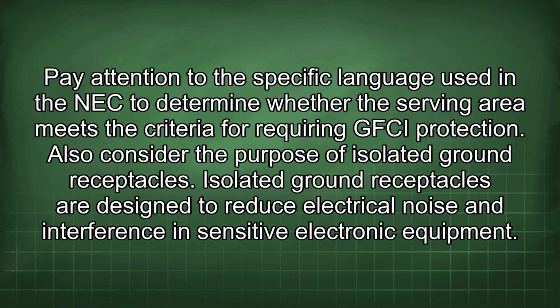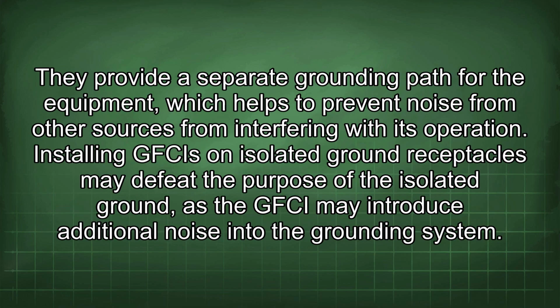Pay attention to the specific language used in the NEC to determine whether the serving area meets the criteria for requiring GFCI protection. Also consider the purpose of isolated ground receptacles. Isolated ground receptacles are designed to reduce electrical noise and interference in sensitive electronic equipment. They provide a separate grounding path for the equipment, which helps to prevent noise from other sources from interfering with its operation. Installing GFCIs on isolated ground receptacles may defeat the purpose of the isolated ground, as the GFCI may introduce additional noise into the grounding system.